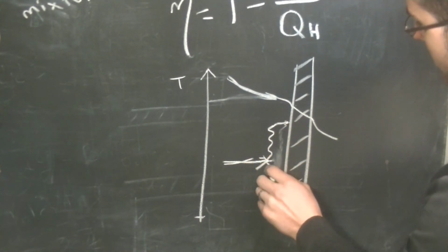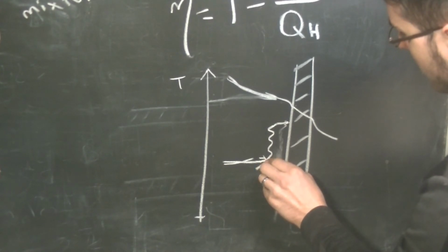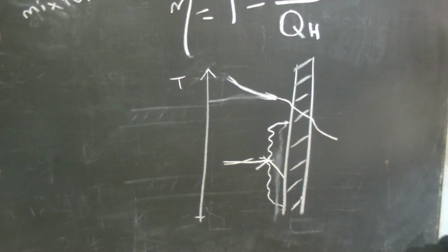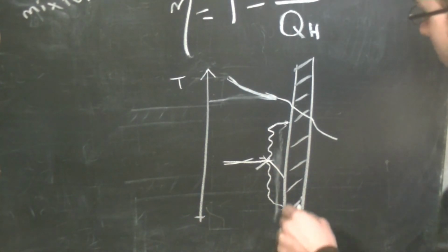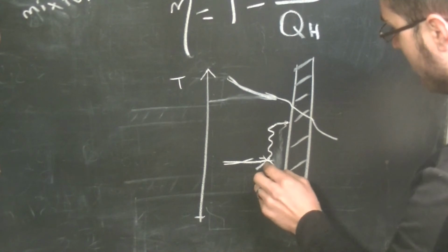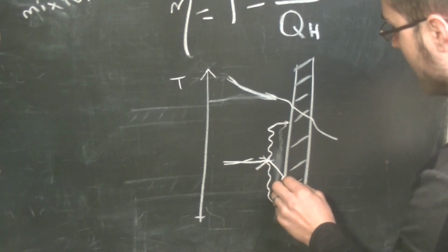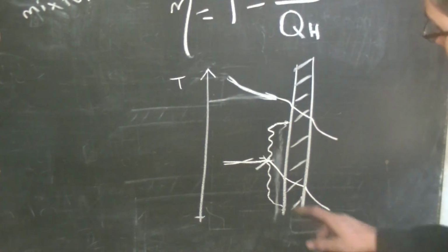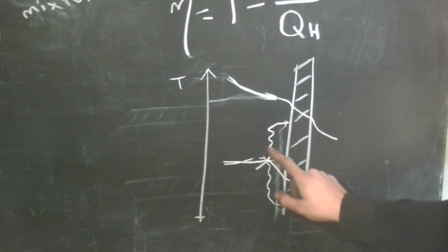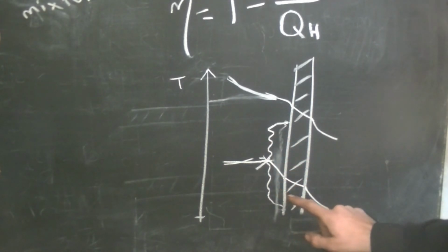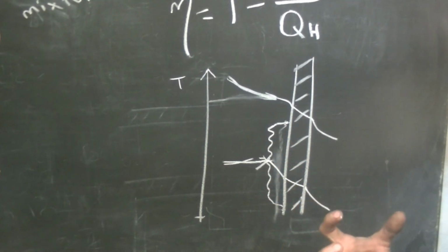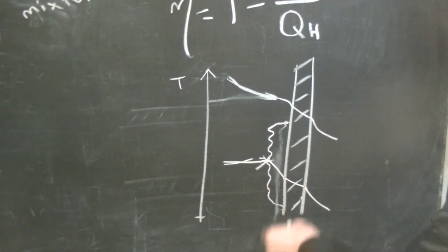This heat will go down really quick because liquid water transfers heat out very well, and then it has to also go through the wall, and so you can see that there's two drops of heat. The liquid water sucks the heat out, which then transfers that heat to the wall better. So you don't want condensate because of this feature.